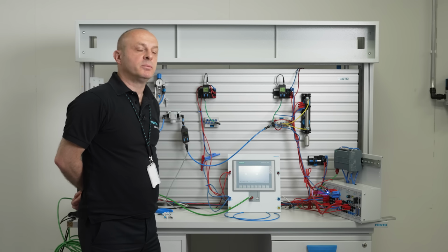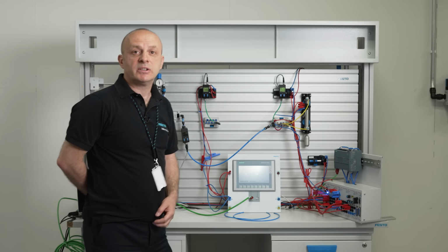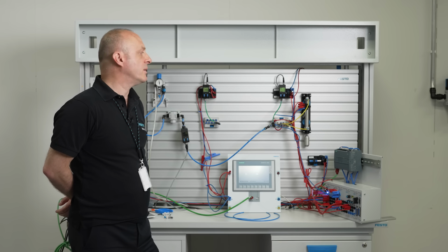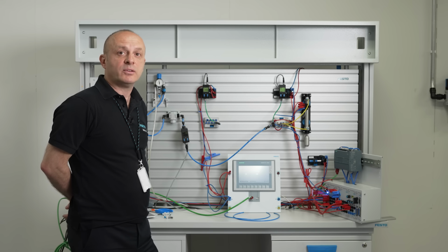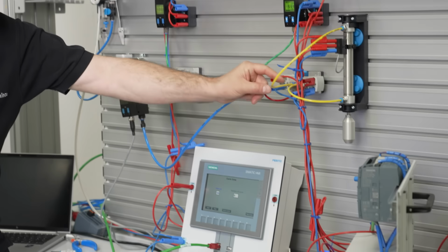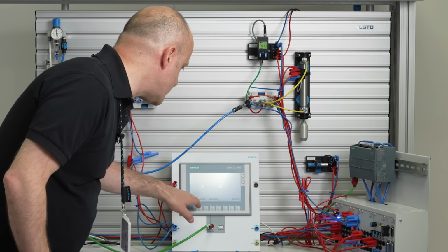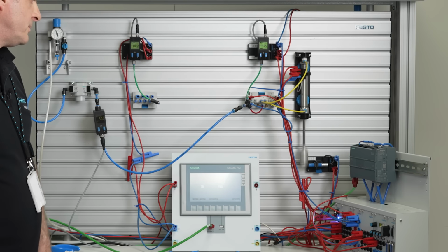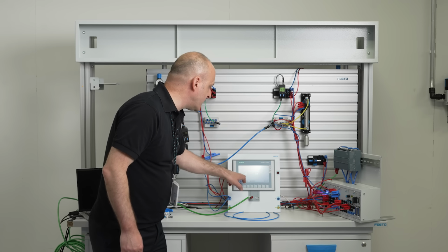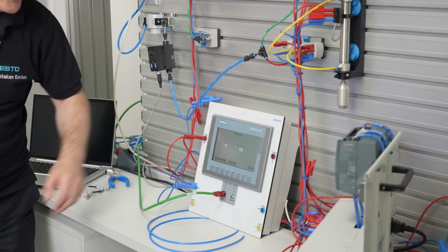In this example, we would like to see whether the tube length between the valve and cylinder can create any issues, breakdowns, or affect the number of cycles on machines. Let's have a look. I've got these yellow tubes between the valve and cylinder. I will start the cycle. Basically, in 10 seconds, the cylinder has advanced and retracted 32 times.